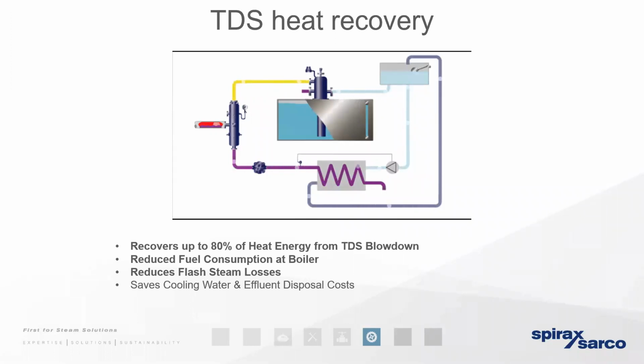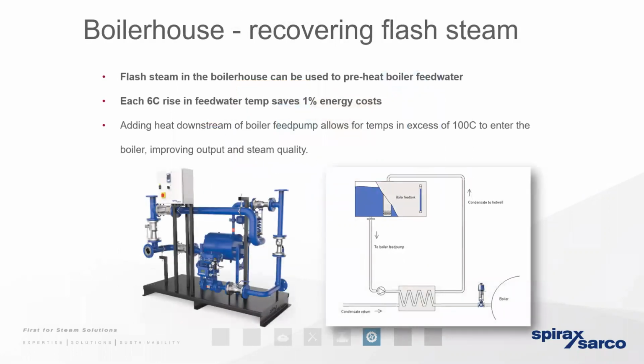Again, a very good area where we can retrofit a solution to bring around an attractive payback. But there are always going to be certain areas where we know we're going to have a lot of flash steam, and that's down to the mass flow of condensate and the high pressures that we may be using that condensate or steam at. So we know that flash steam needs to be vented to protect condensate pumps and pipes from overpressure.